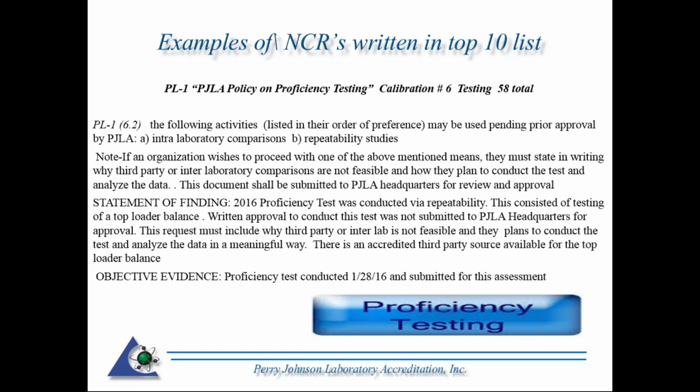So, other areas of proficiency testing with new labs: basically before you're even accredited, you have to do an approved proficiency test within the realms of PL1. Again, we go over approved methods of proficiency testing. We allow interlab, so that's if two or more accredited organizations calibrate or test the same artifact or sample and compare, and this is the part I like to emphasize, and compare the results in a meaningful way. So if you're doing an interlab proficiency test with another organization, we require more than here's their results, here's our results. We need to see some sort of analysis of the data and hopefully some predefined limits of acceptance that show either the results compare to each other or they do not.